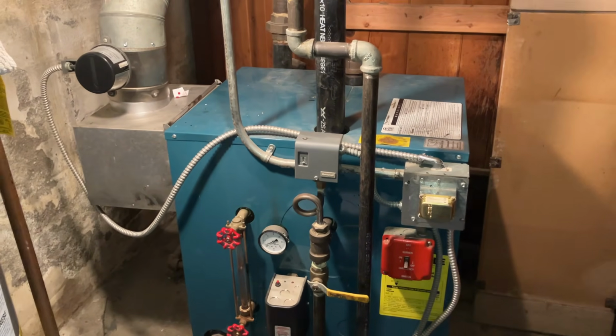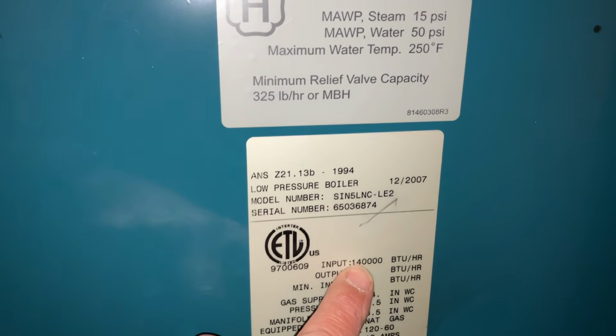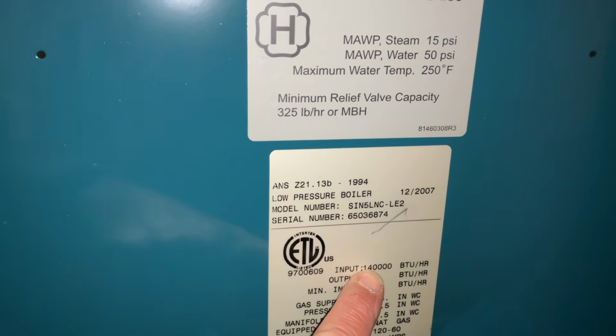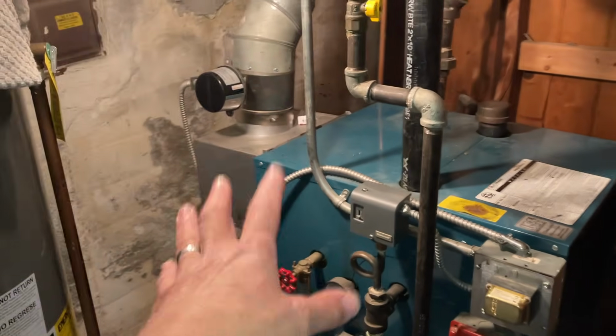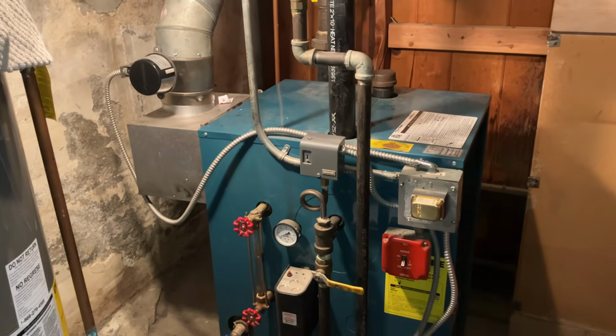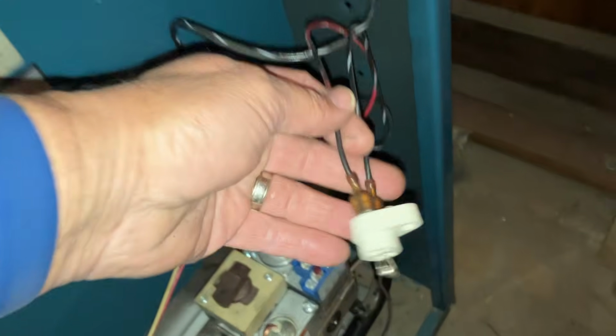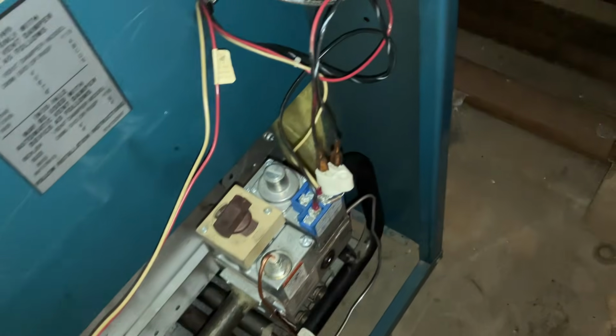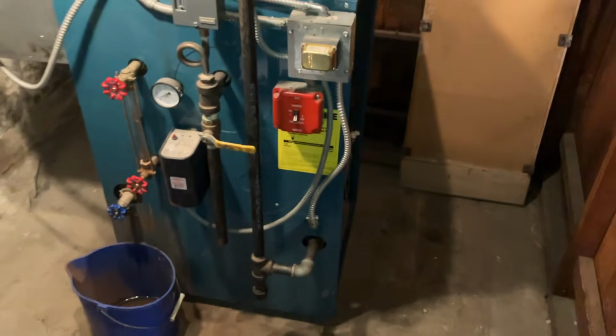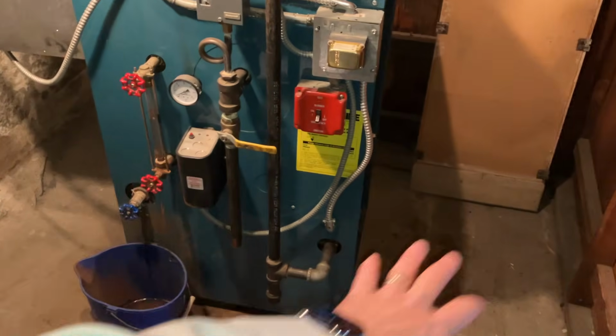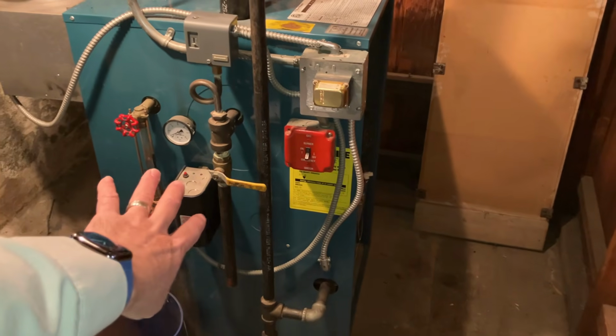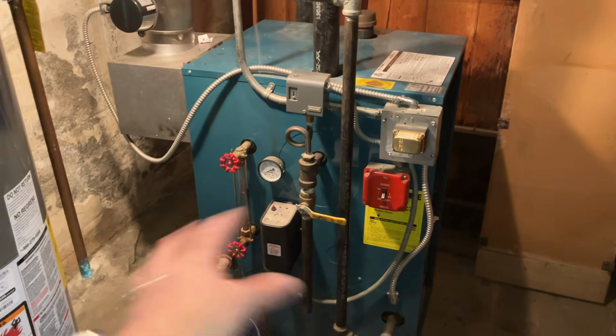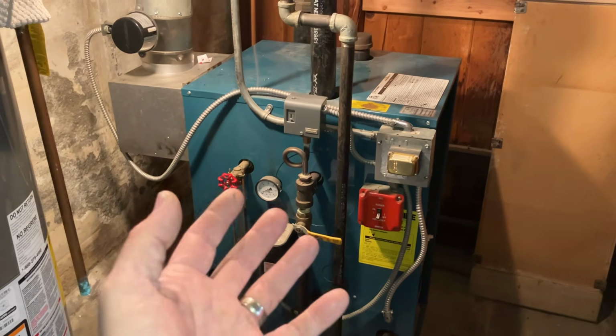Check this out, guys. All right, ladies and gentlemen, we got a U.S. Boiler, Burnham SIN 5, 140,000 BTU gas-fired steam boiler with a manufacturer date of December 2007. I was at this job yesterday, late afternoon, no heat. Found that the rollout switch was all burnt up. Tons of carbon. It's like black little cotton balls scattered throughout the whole base of the boiler, underneath the main burners, inside the combustion chamber, all sooted up. And essentially we have a carbonized boiler.